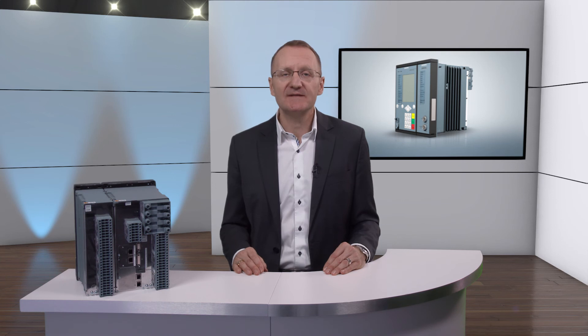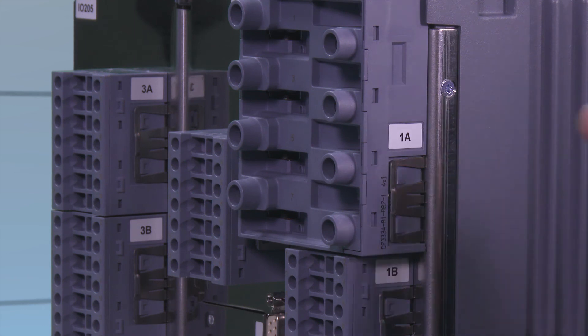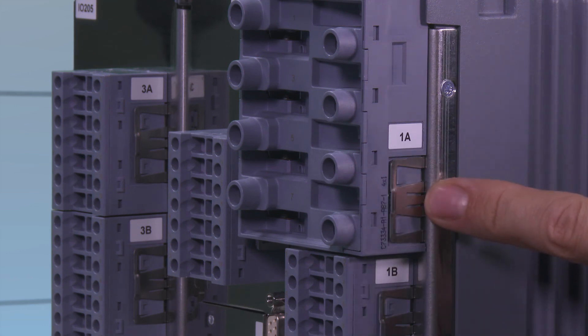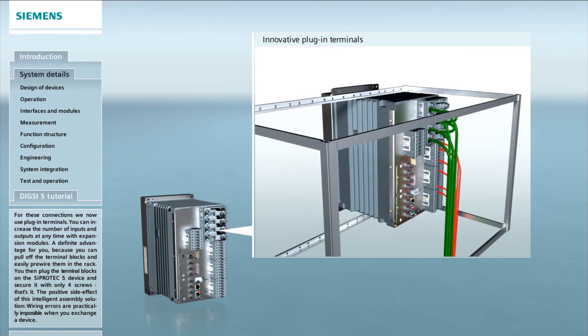Further information on the assignment of terminals can be found in the device manual. All terminal blocks have spring clips on the sides, which can be used to easily remove all process connections from the device without having to disconnect the process cables. This makes it possible to pre-wire the cabinets in which the devices will be built into, and to mount the protection devices and connect the terminals on site.